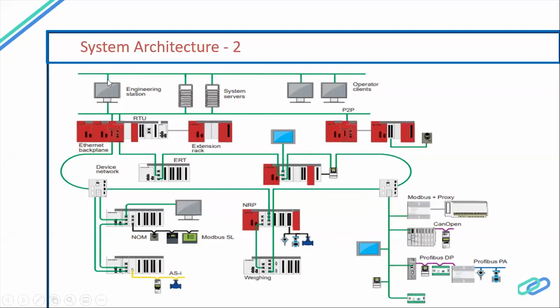After that, the top layer is for your engineering station. As I am explaining, there are two servers. So what is the role of the engineering station? The engineering station is basically used for PLC programming, if any SCADA modification is required, or if some new report needs to be implemented. Anything required, we do through the engineering station, because if we use the operating client, we need to disturb the operator again and again, asking them to give the PC.